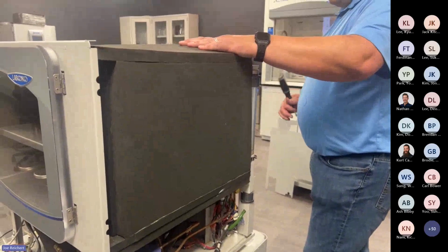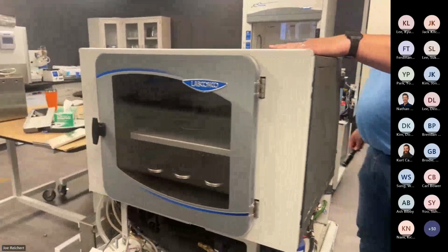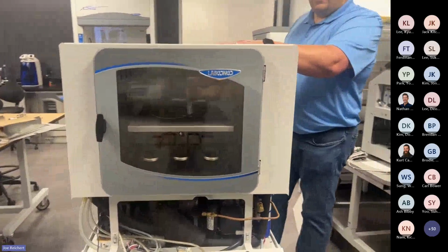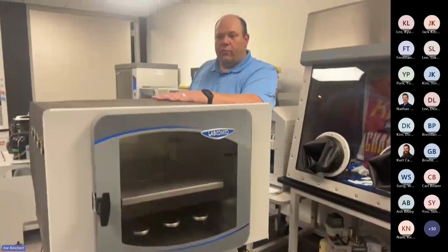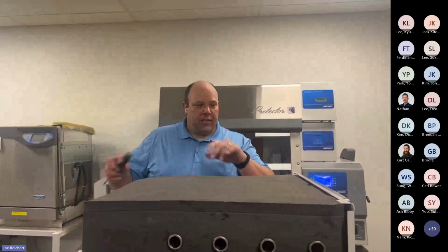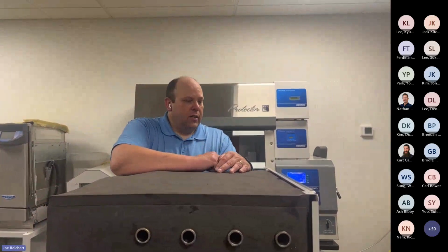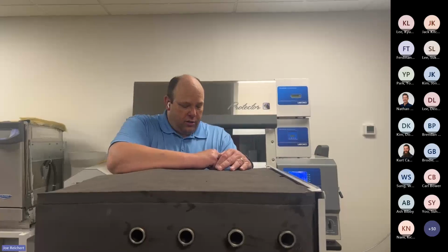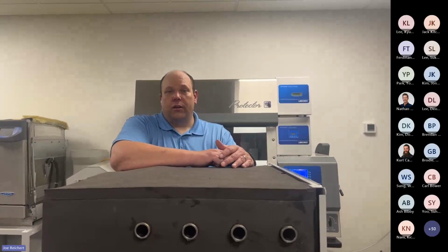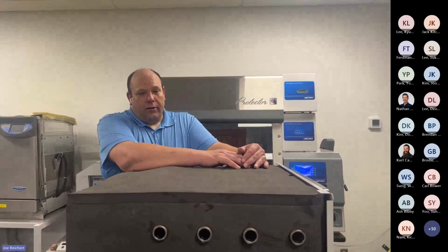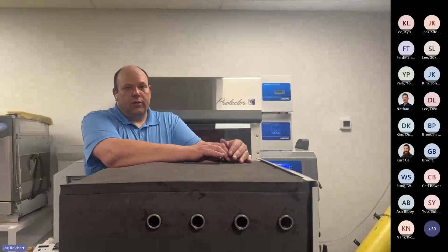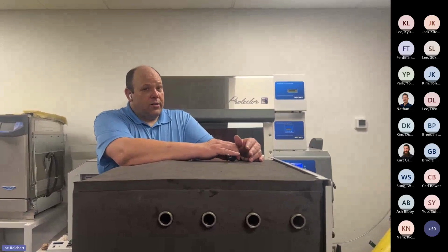The stoppering tray dryer is not a speed demon on cooling. It's got a collector that goes to -84, but the shelf will reach -55. But the IQ/OQ on that is 5 hours. There was an update to the system not that long ago. We made the refrigeration a little stronger, could put a larger compressor in on the second stage, and that has helped tremendously with speed. But our IQ/OQ is still at 5 hours. Now, usually the units can get to full temperature, usually within 3 hours now.